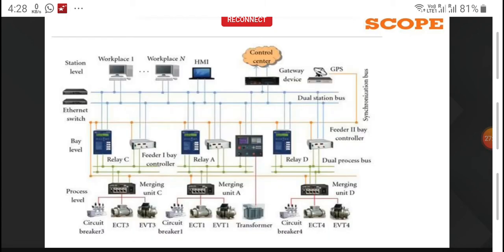If you go to the actual configuration of the digital substation, you can understand the different things in it. You can see here the circuit breaker and the electronic CT or optical CT. There are two different CTs, or electronic VT or optical VT. These are all connected through optical fiber to the merging unit. The merging unit is mainly a unit which conditions the signals from the CT or PT. If the signals are not proper, it conditions them and sends them in a proper way to the relay.